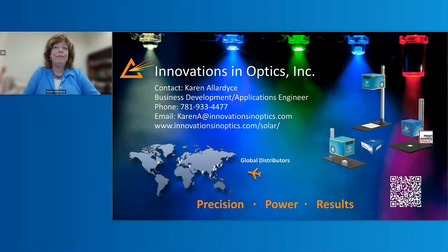All right, and I think we have time for one more question here. Is the LumiSun 220 capable of both AM0 and AM 1.5G? Yes, it is. So that's something you want to look for out in the solar simulator world when you're shopping for one. Those two spectra are necessarily different. AM0 is, of course, space related, for satellite testing or anything that has not had the attenuation of the Earth's atmosphere.